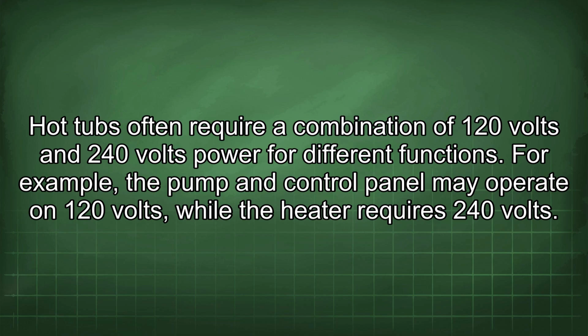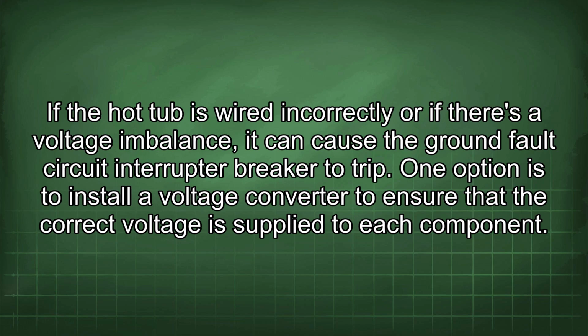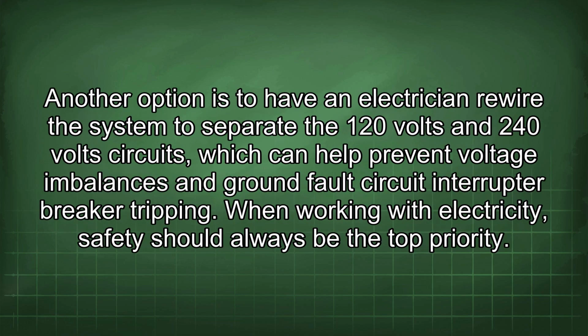Hot tubs often require a combination of 120 volts and 240 volts power for different functions. For example, the pump and control panel may operate on 120 volts, while the heater requires 240 volts. If the hot tub is wired incorrectly or if there's a voltage imbalance, it can cause the ground fault circuit interrupter breaker to trip. One option is to install a voltage converter to ensure that the correct voltage is supplied to each component. Another option is to have an electrician rewire the system to separate the 120 volt and 240 volt circuits, which can help prevent voltage imbalances and ground fault circuit interrupter breaker tripping.